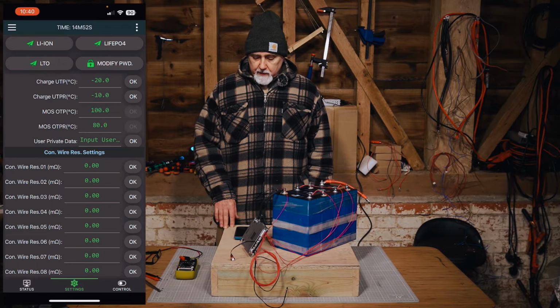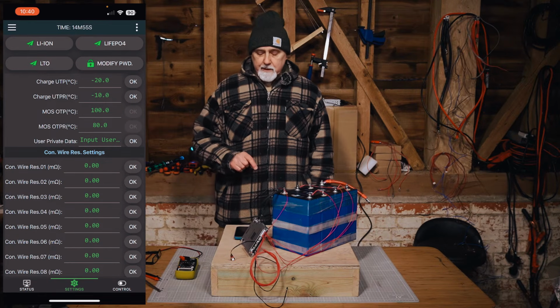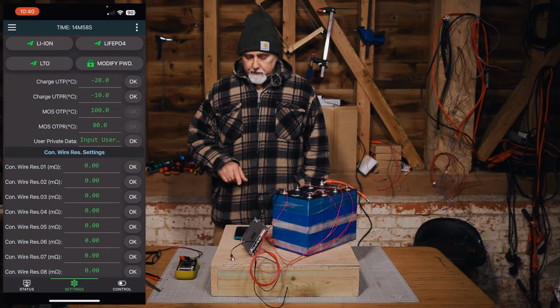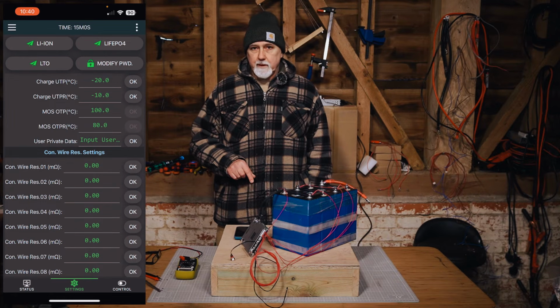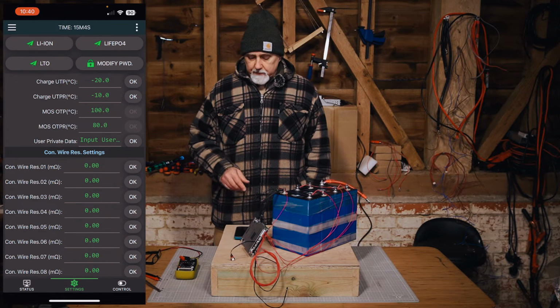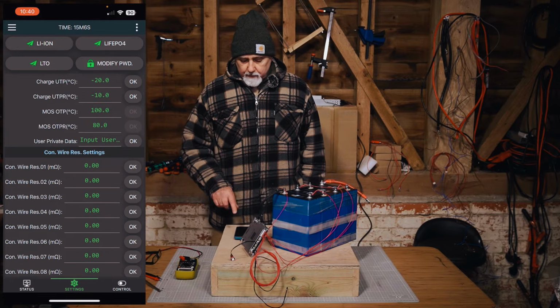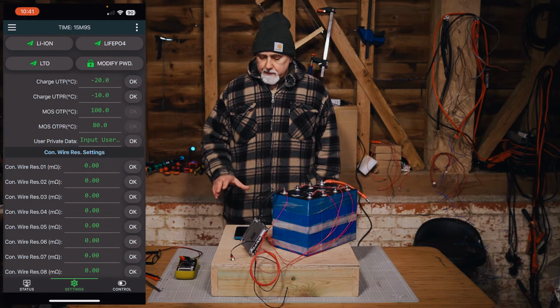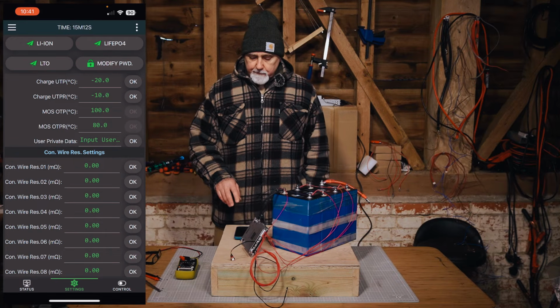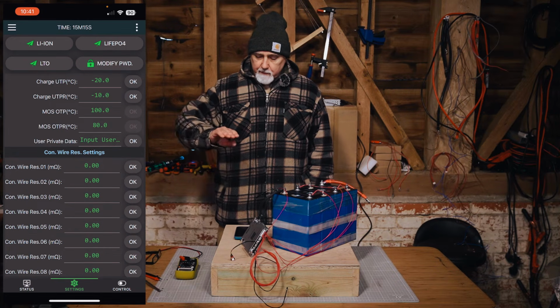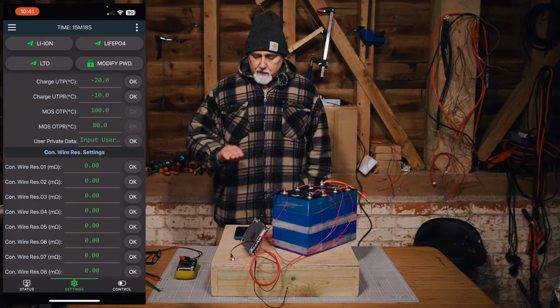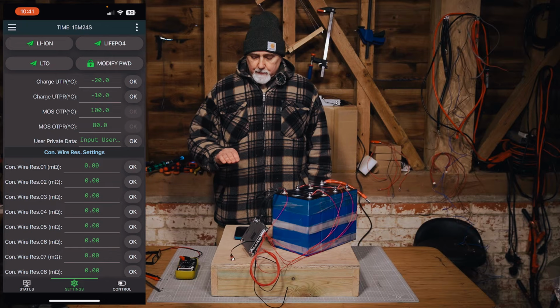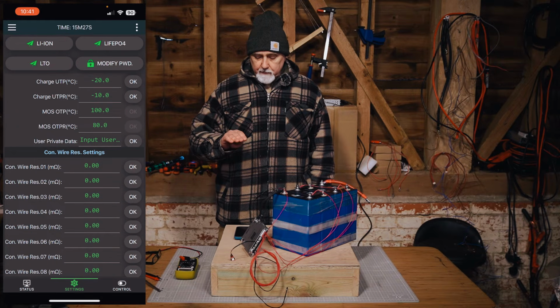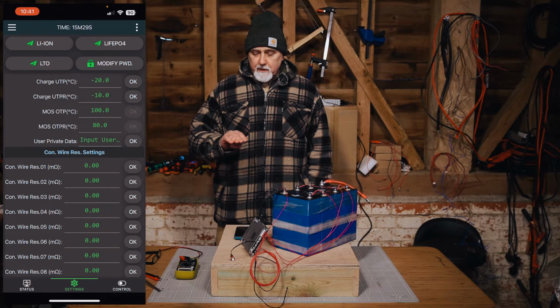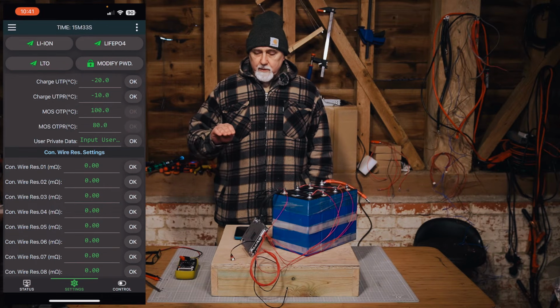So the UTP we set to 5 degrees, and the UTPR, the reset, we set a few degrees above that, probably 8 or so degrees. Let me explain why this matters: if the temperature drops and drops and you hit 5 degrees centigrade, it stops allowing charge to protect the cells. Then the temperature needs to rise back up, say to 8, if you set the UTPR at 8, before it allows charge again.